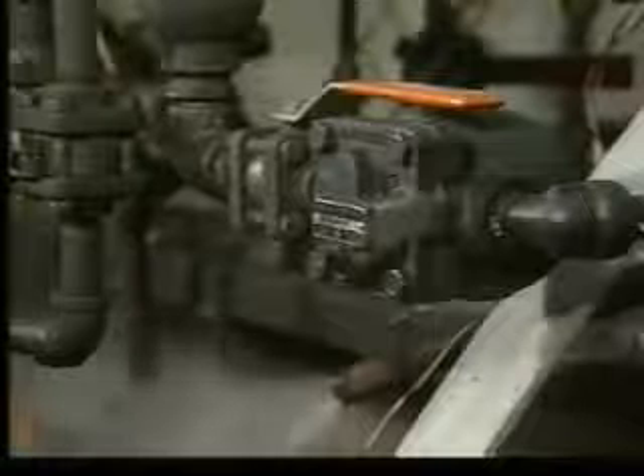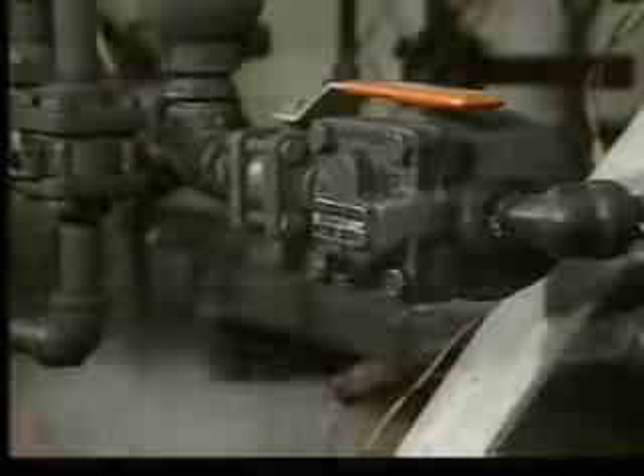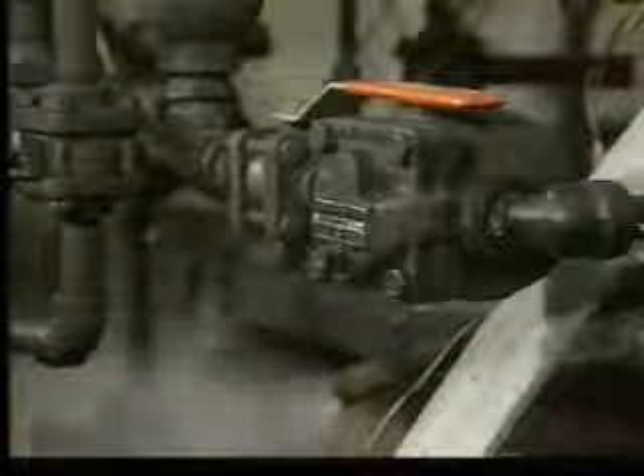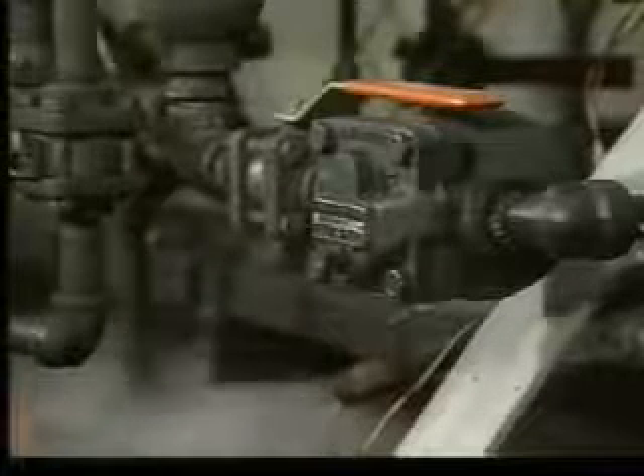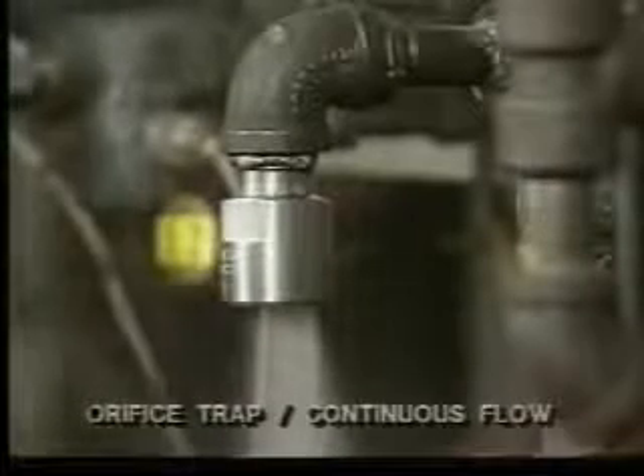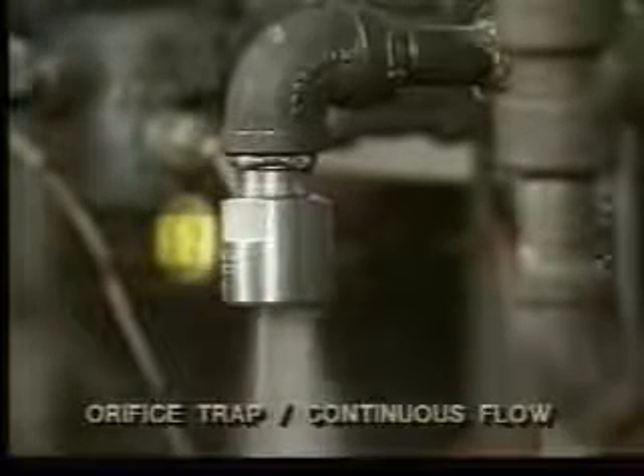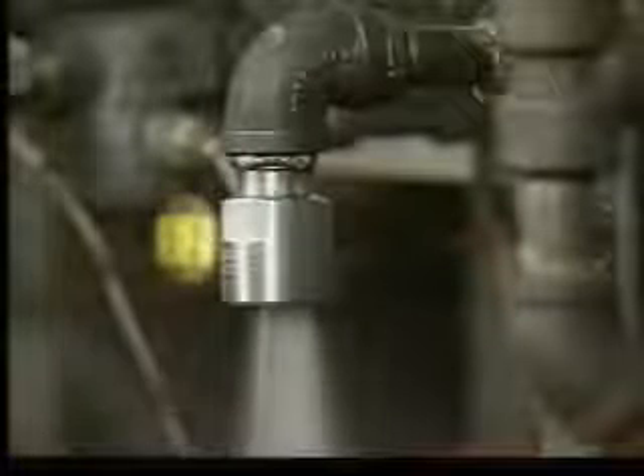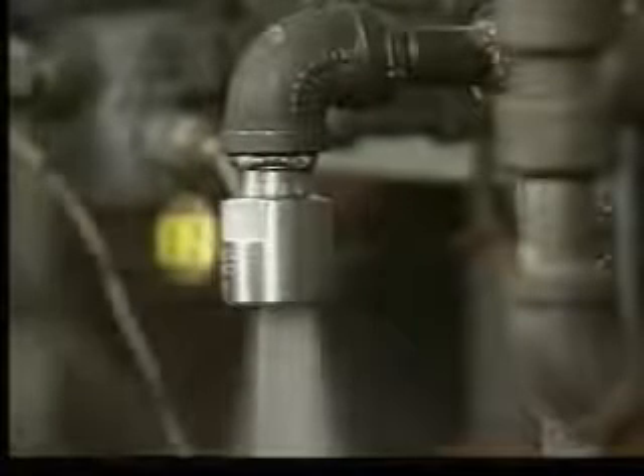The float and thermostatic trap, or F&T, is a continuous flow trap. Listen for its continuous modulating sounds. The orifice trap is a fixed orifice device. When functioning normally, its continuous flow sounds like this.